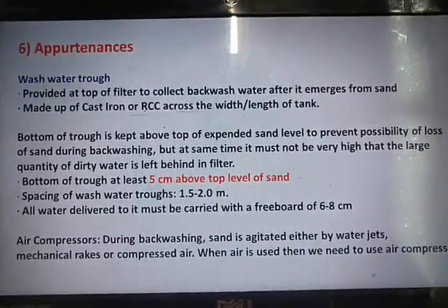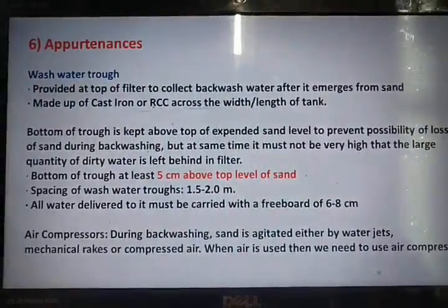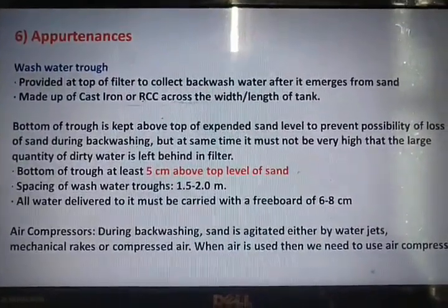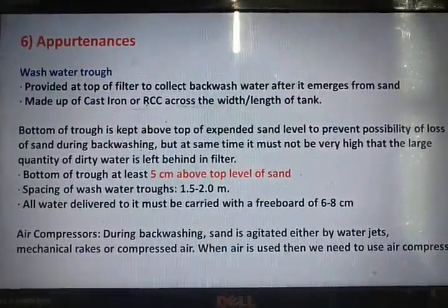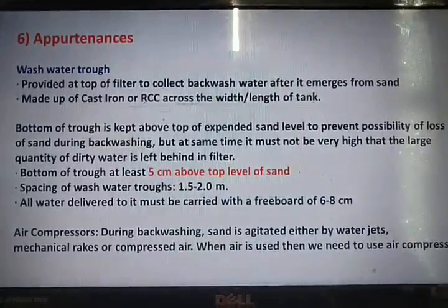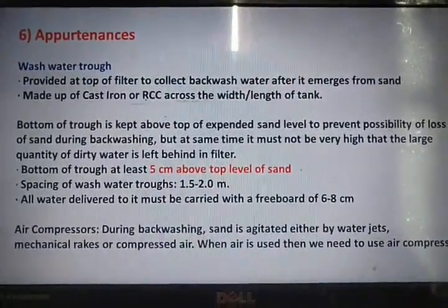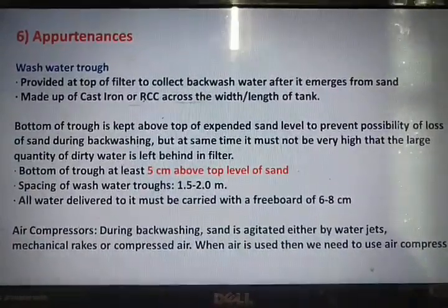Okay, and the bottom of the trough should be at least 5 cm above the top level of the sand. Okay, and spacing of wash water troughs will be in the order of 1.5 to 2 meter. All water delivered to the troughs must be carried with a freeboard of 6 to 8 centimeter. Okay, then it also has air compressors.